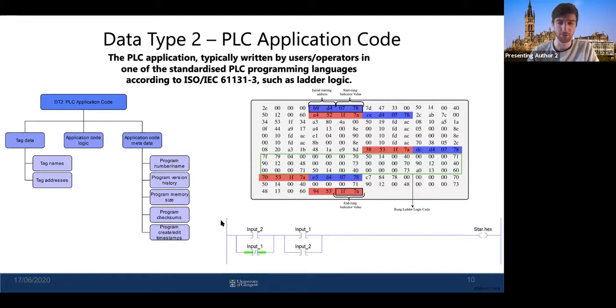Interestingly, we could get some checksums, which I should stress are vendor specific, so the strength of these checksums is maybe not the same across the board between different PLCs. But also interestingly, we were able to get quite a lot of timestamp data, which in forensics we commonly refer to as MAC timestamps. So this is modified, accessed, and created timestamps for a specific piece of data. PLCs operate in a little bit of a different way. There's some different terminology, so trying to sift through that and figure out what terminology is transferable between IT and ICS is really important for forensic investigators.